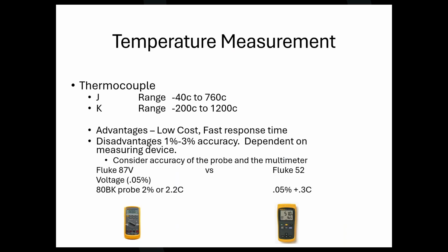Oh, all right, that device will test to 900 degrees Celsius. That's hot. How many of you ever looked to see what your probe limitation is? Your probe may only go to 200 degrees Celsius, or 50 degrees Celsius. So you plug in your probe, test it, and go, wow, that's broke, it ain't heating up hot enough. You've got to look at your probe, because your probe is now your limiting factor of the thermometer that's in there.